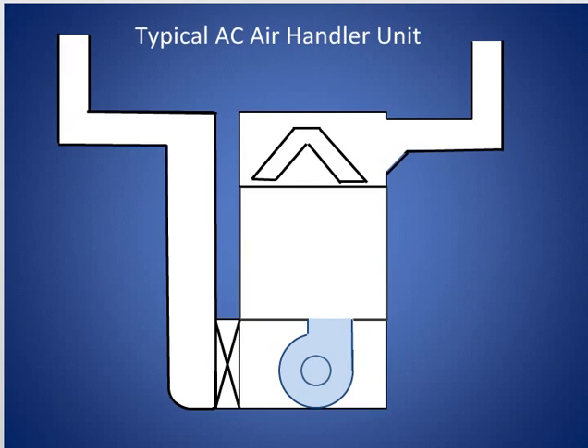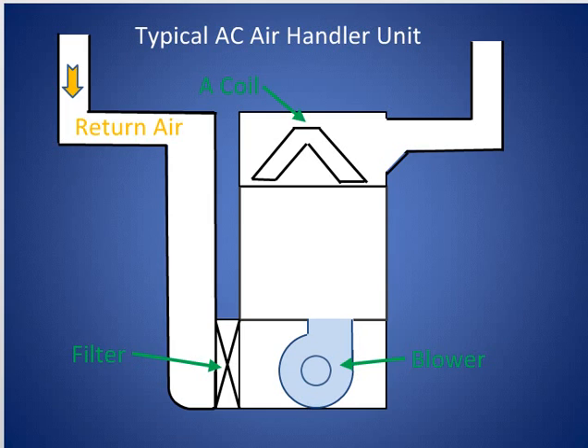To understand duct design we need to understand the basics of air flow. Return air is where the air goes into an air handler — this is a typical air handler unit. It goes through a filter, and there's a pressure drop across the filter. It goes into the blower, which puts pressure on the air, and then it blows up through the A-coil or the heat exchanger. Then it goes out into the supply air system, and if the duct work is designed correctly it doesn't interfere with the air handler producing the right amount of air through the heat exchanger, and everything works properly.